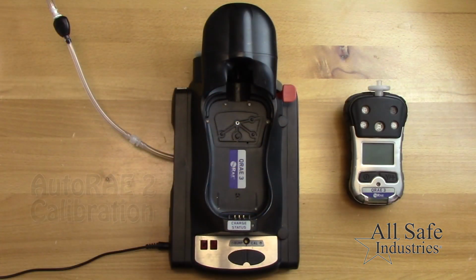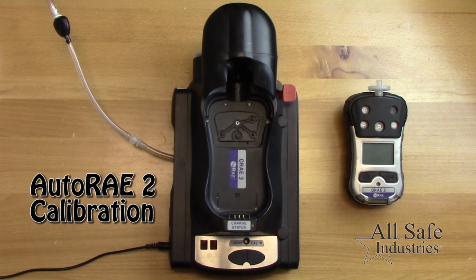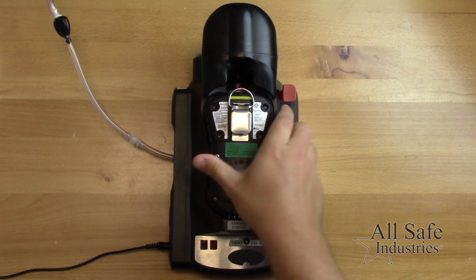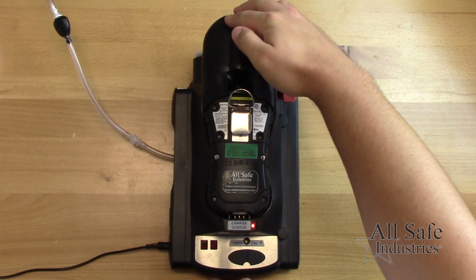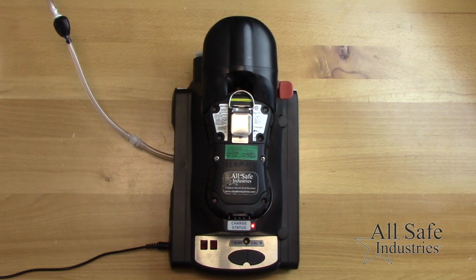To calibrate using an AutoRAE 2 calibration cradle, start with the QRAE3 turned off. Place the meter face down on the cradle and close the capture mechanism. This will power up the meter and begin the warm-up sequence. Once both lights are solid green, press the cal button. Once the calibration is complete, the cal light will display solid green for pass or solid red for fail.